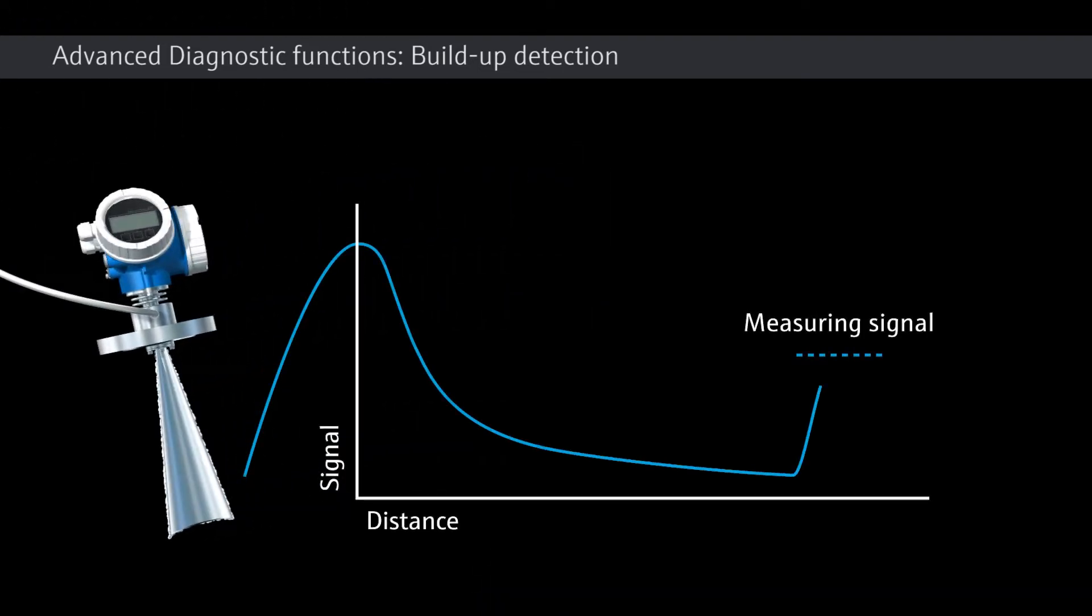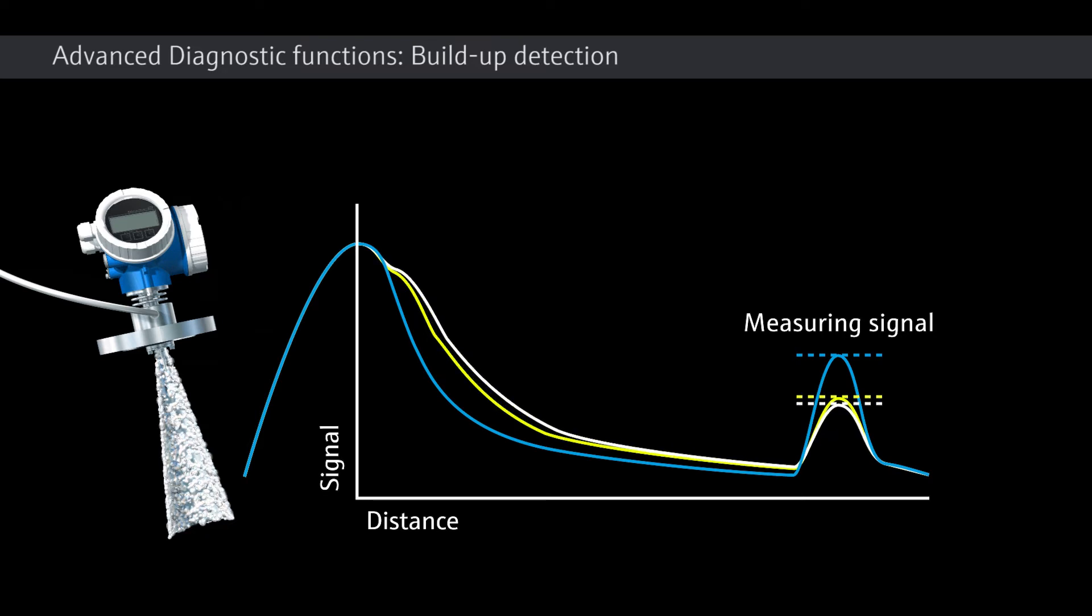The new advanced diagnostic functions of Micropilot easily monitor process and instrument data. The example shows that the signal intensity attenuates as the buildup increases. If the signal intensity becomes too low, reliable measurement is not possible anymore. Only cleaning of the antenna can restore reliable measuring capability.